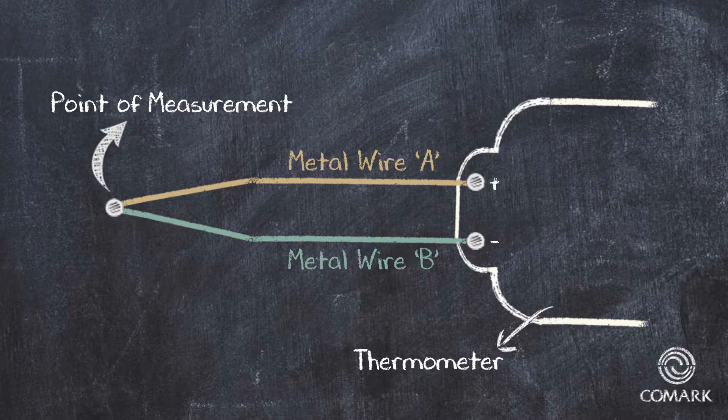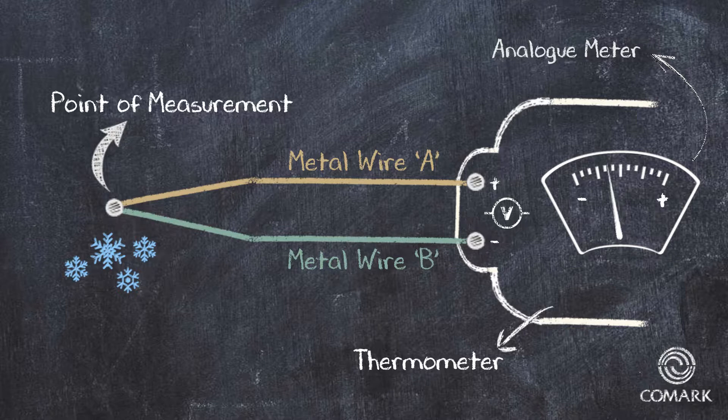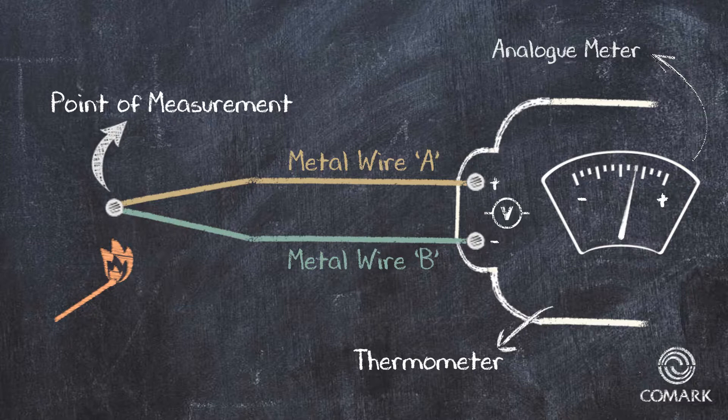As the two metals in the thermocouple are heated or cooled, they produce a very small but measurable voltage. If we imagine this voltage on an analogue meter, we would see a negative voltage and movement to the left if the point of measurement is exposed to something cold. And conversely, we would see a positive voltage and movement to the right if the point of measurement is exposed to something hot.